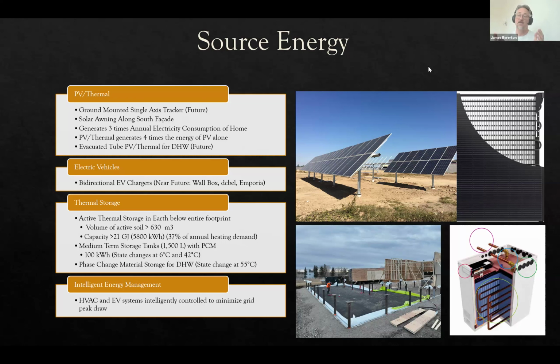We had an encapsulated phase change inside it, with ABS pipes capped off at both ends, with a little bit of air so it doesn't thermally expand and blow up. That goes inside the liquid, and we shoot the 3/4 inch PEX pipe down beside it. That's how we did the circulation inside the energy pile. So it's not actually a closed loop in the pile. The pile itself is the circulating loop, forming the basis for our circulation.